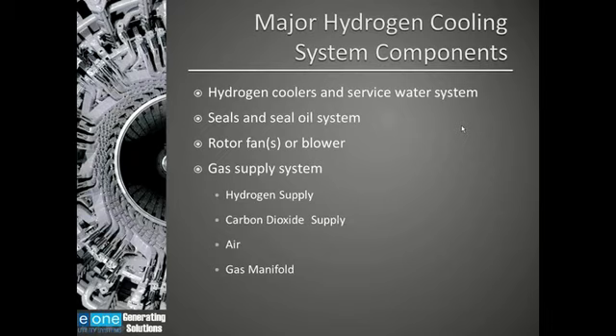Major hydrogen cooling system components are the hydrogen coolers and the service water that feeds the hydrogen coolers, the seals and seal oil system, the rotor fans and blowers, and then the gas supply system, which will consist of hydrogen supply. This could be tanks, or it could be a bulk system, could be a hydrogen generator that generates its own hydrogen. Carbon dioxide. Throughout my presentation, I will be using carbon dioxide as a purge gas, although there are some plants and some OEMs that will use a different gas, such as argon, for a purge gas. Then there's the air supply, and then there's a gas manifold that allows you to degas the generator and control the hydrogen during normal operation of the generator.